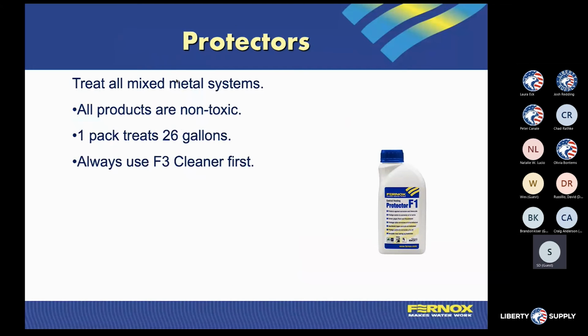The main product that we sell on the protectant side, when we're talking about bringing our system out of a flush: we've cleaned the system out, we've got it as flushed out as we can. The next step, when we get the system bled out and get all the air out of the system, is we're going to add our protector into that system mix. So our F1 does two things. The first thing it does is it doesn't allow anything to stick. You have to think of Fernox F1 as essentially a layer that goes inside your whole system, and now that won't allow your hardness to stick or plate to the inside of your system. So that buildup will no longer be able to happen.